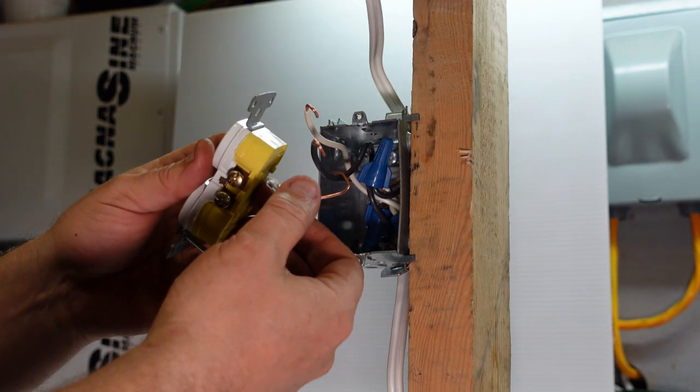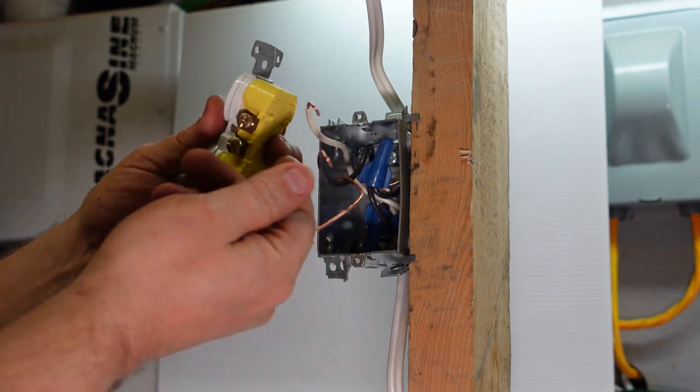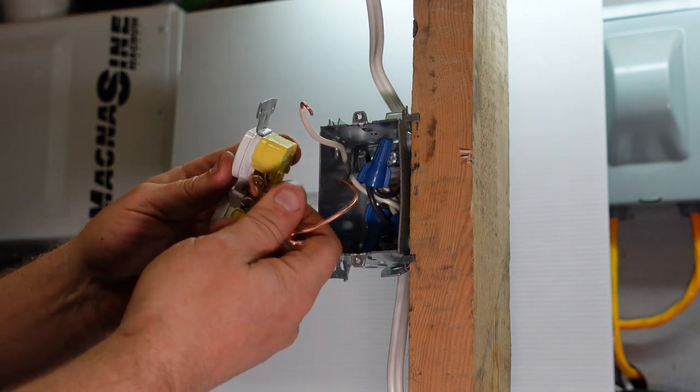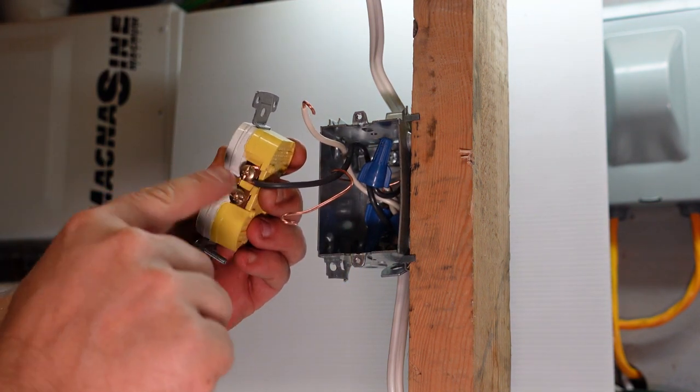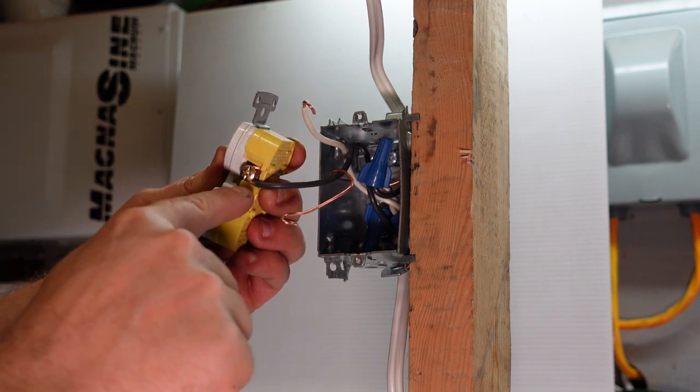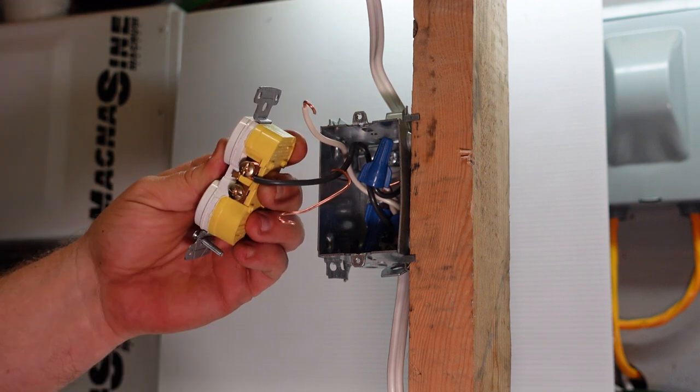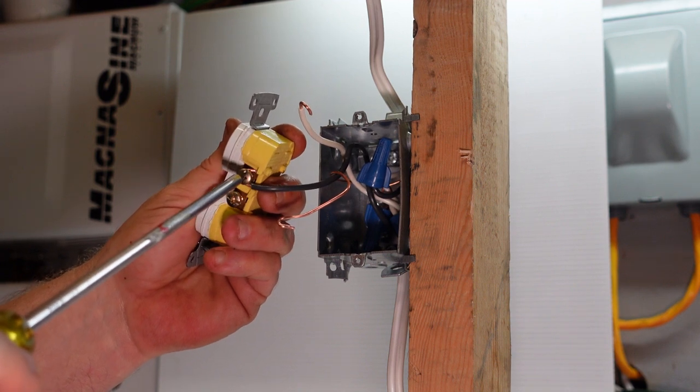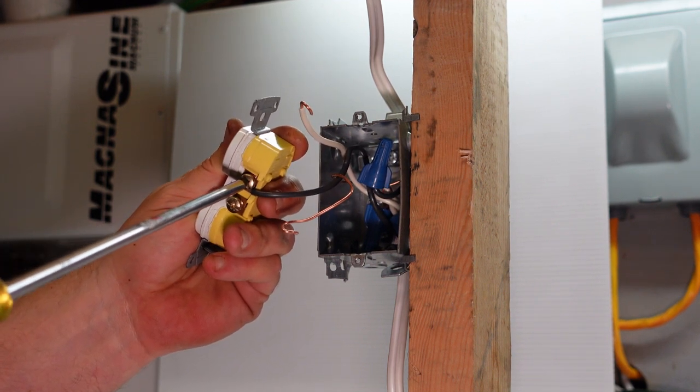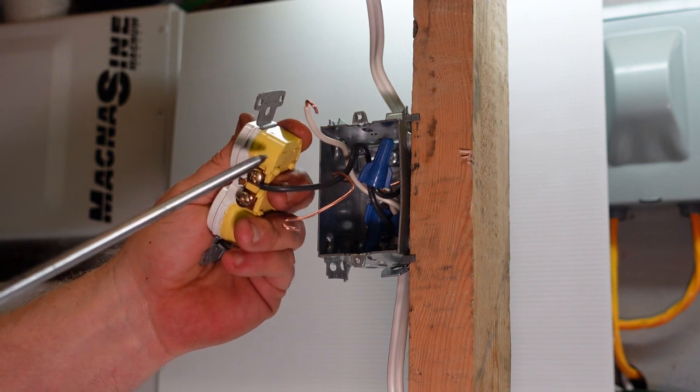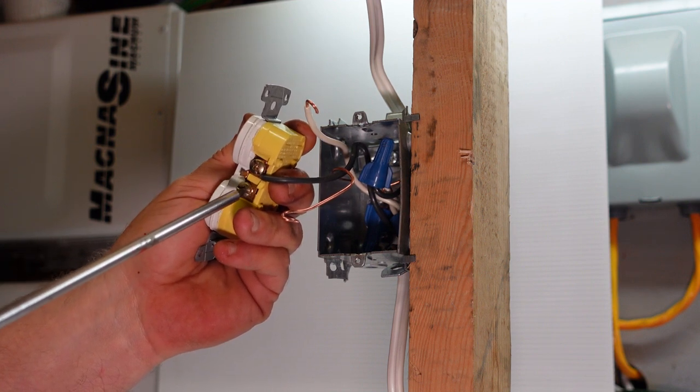Now the important part: when they go on the receptacle, the hook needs to face this way, not the opposite way. The reason for that is because when we tighten down these two screws, it pulls the wire into place. If we go the opposite way, it will tend to want to pull the wire off of the receptacle, and that is actually not a good connection.